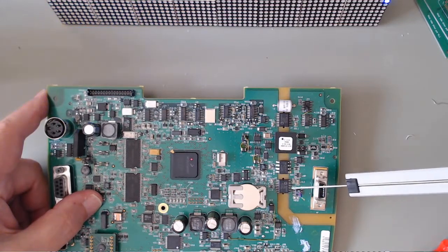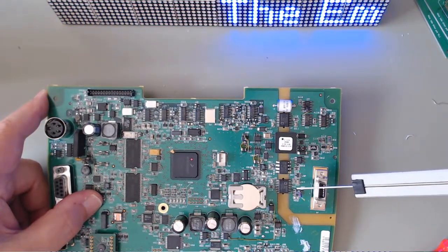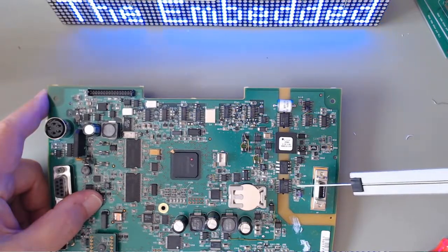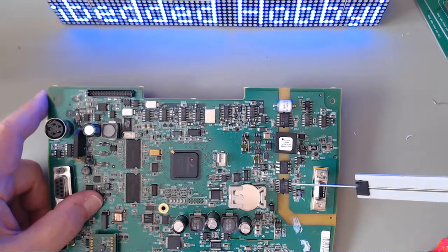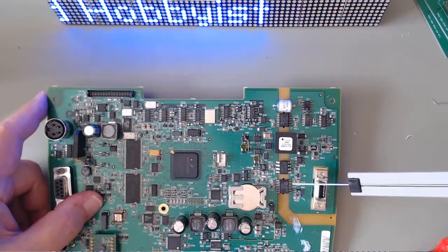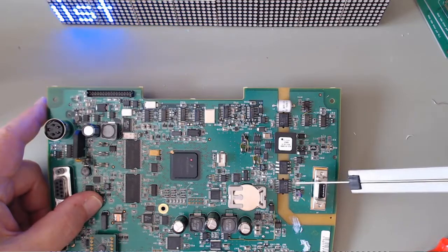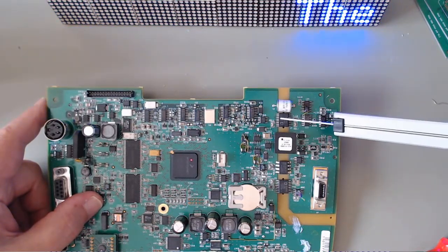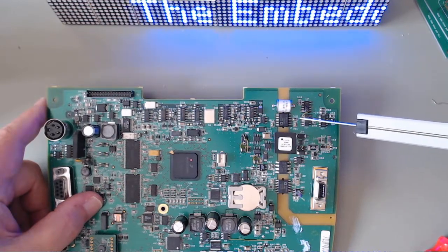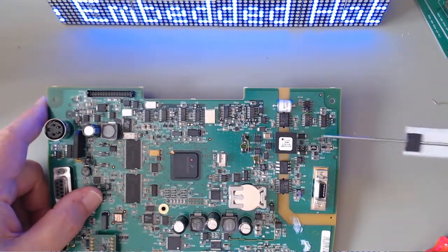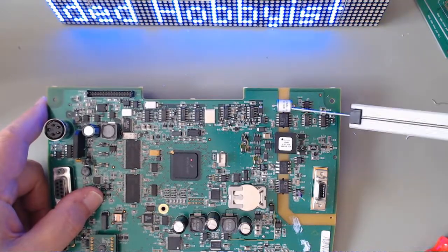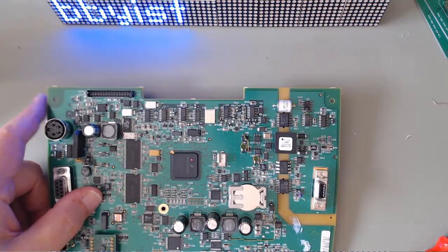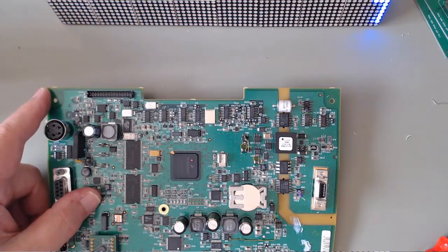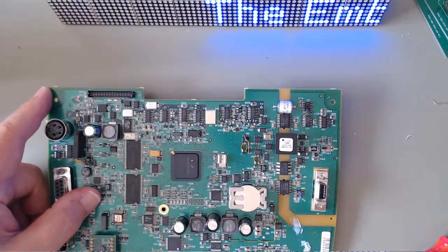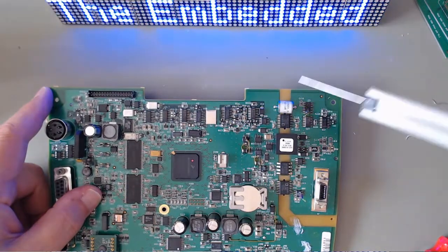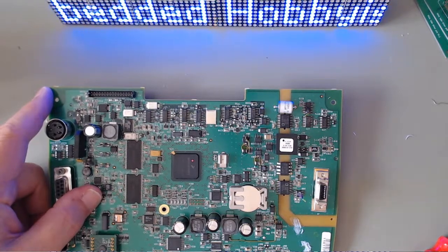digital bridges, so digital signals from here can migrate to here, and there are 3 going in one direction and 1 coming back. And as you can see, they are rotated round. So in one of these there'll be 3 data signals coming this way and 1 data signal coming back, and on the other one there'll be 3 going this way and 1 coming back. So it's got 4 channels this way, 4 channels that way, and a spark gap, so that if anything, like a nurse or someone comes up and she's charged up with some static by accident, she'll touch the connector, or as the connector goes in, any high voltage static will discharge through this and be removed before it's connected to the patient.